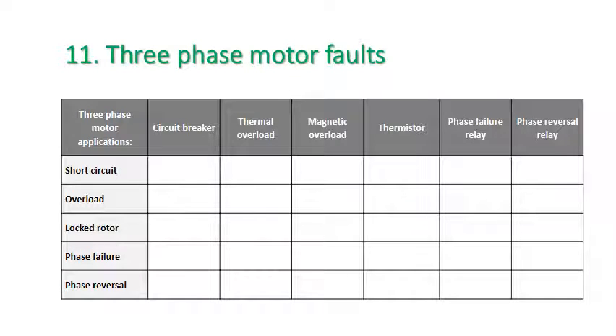So we have here a table of circuit protection devices and potential faults. We've got short circuit, overload, locked rotor, phase failure and phase reversal, and the protection devices are circuit breaker, thermal overload, magnetic overload, thermistor, phase failure relay and phase reversal relay. So we're going to make some choices here of what sort of equipment we're going to use to protect against these different faults. So the first one is short circuit, and what are we going to choose?